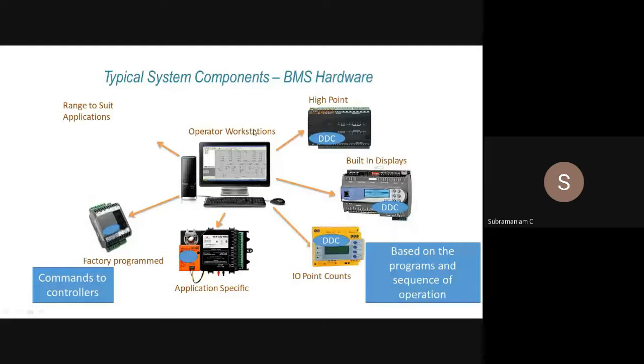And the typical system architecture: the BMS hardware, where you have the BMS workstation. All these things will communicate. You have your application specific controller. You can have factory programming. For example, when you buy a VAV box, the factory itself will set the minimum and maximum CFM setting. That can be changed at site, but how many things? You have 200, 400 VAV boxes.